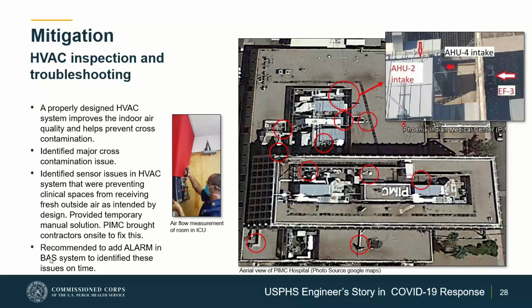Because of COVID, a lot of facilities made temporary modifications to their HVAC systems. We wanted to make sure those modifications are documented and in compliance with CDC guidelines. For example, maintaining distance of exhaust from operable windows or outside air supply intakes, because you definitely do not want to recirculate contaminated air back into clean space.